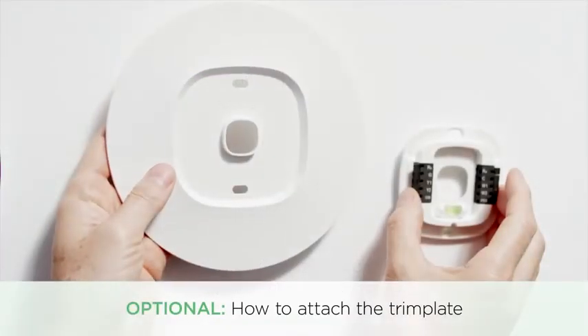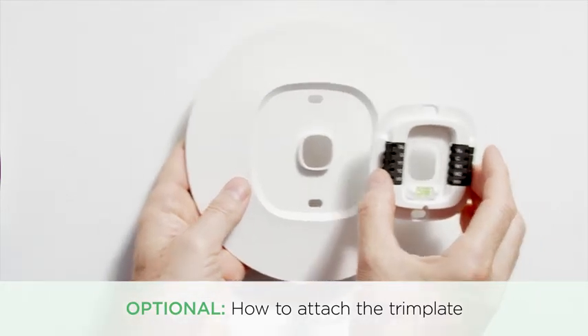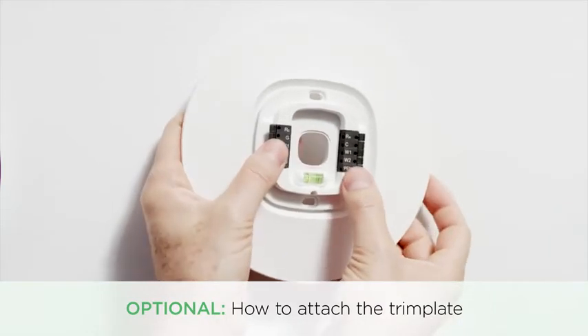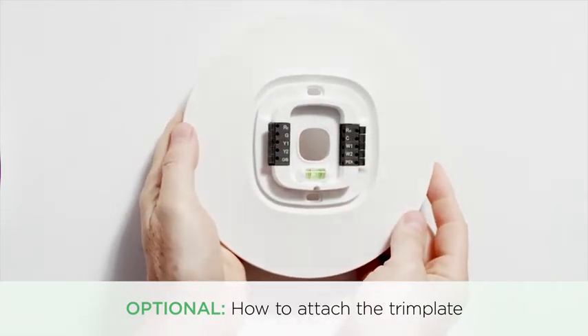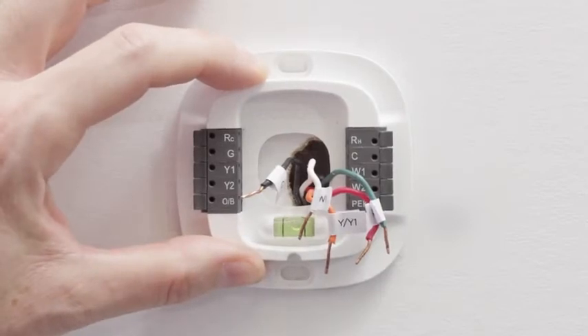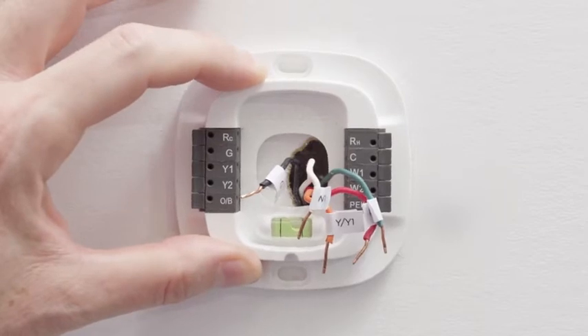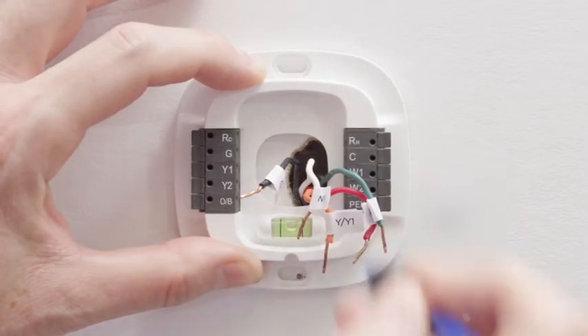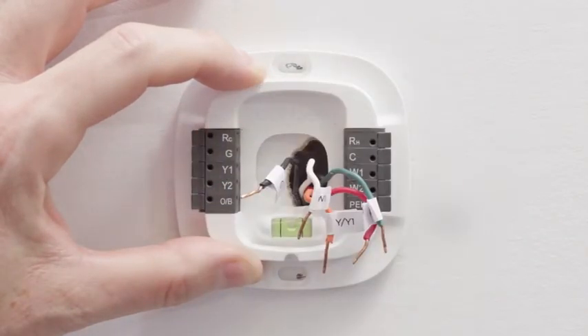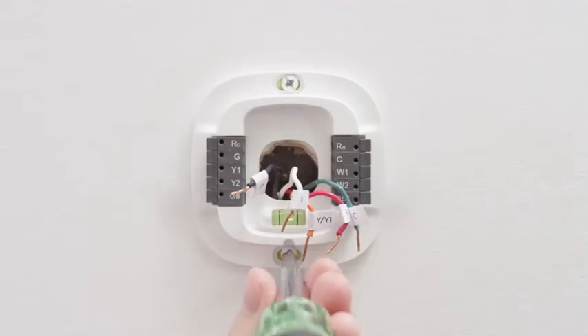Decide if you want to use the large trim plate with your ecobee3 lite. The trim plate is useful if you want to hide paint marks or holes in your wall left by previous thermostats. If you'd like to use the trim plate, align the mounting holes on the trim plate and back plate and press them into place together. The back plate should sit flush against the trim plate when it's attached correctly. Position your ecobee3 lite backplate over the existing wire hole to verify that the previous screw holes are covered. Use the built-in level to level the backplate. Then, using the backplate as a template, mark the location of the mounting holes on the wall with a pencil. Drill 2 holes and mount the backplate using the drywall plugs and screws provided.